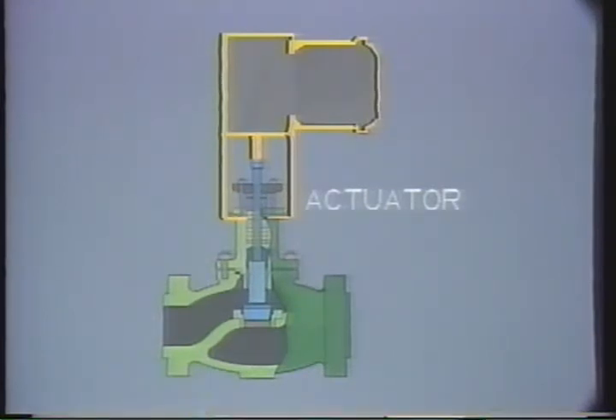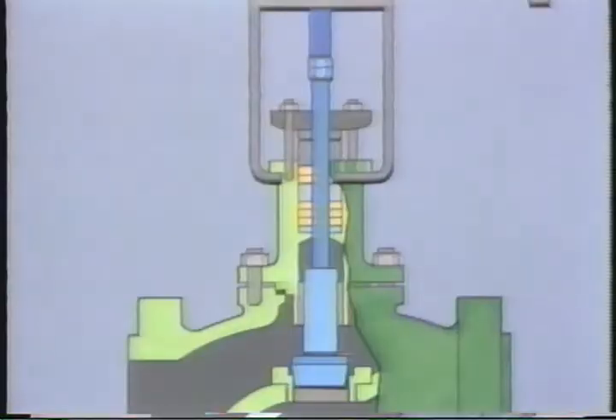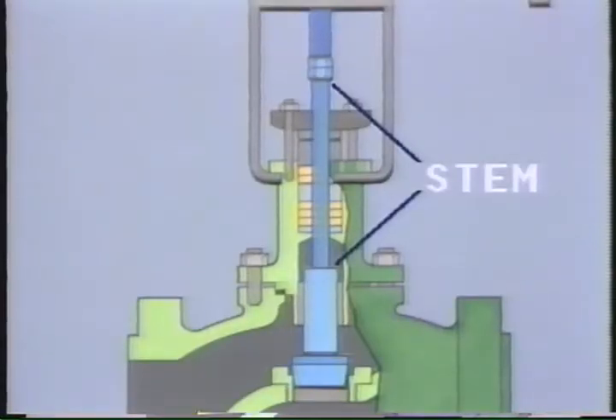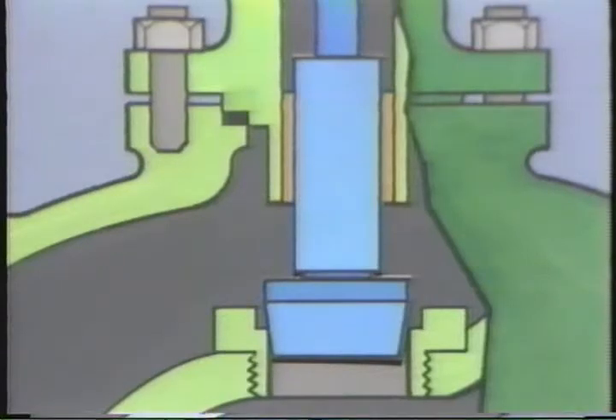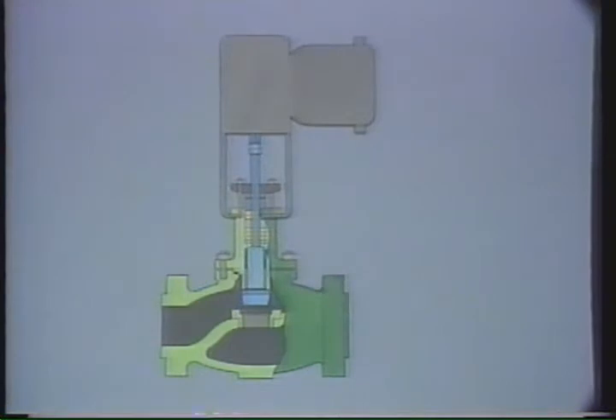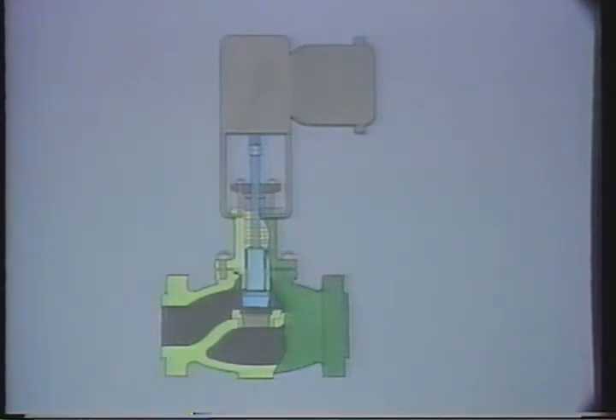The actuator provides for the automatic operation of the valve. The stem is connected directly to the actuator, and attached to the stem there's a plug. When the globe valve is operating, the stem and plug are moved up and down in response to the movement of the actuator. As the stem and plug move down, the plug approaches the circular seat.